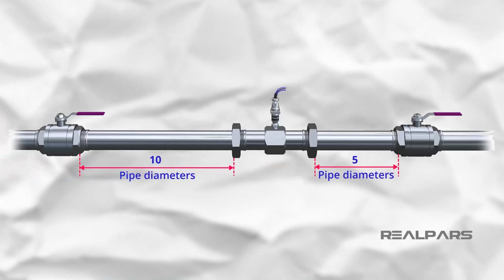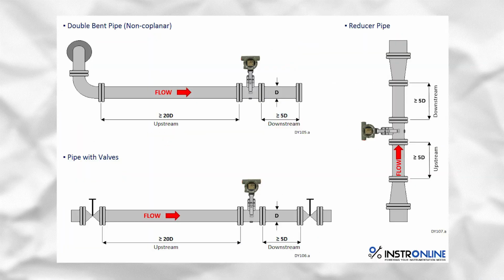To calculate the bore diameter of an orifice, ISO standard 5167 is applied. As an instrument engineer, you should be able to work with related software to do flow element sizing, such as Conval and InstruCalc. The outcome of this software shows the orifice bore diameter and beta ratio, which is the bore diameter divided by the pipe internal diameter. By means of this relation and knowing the fitting installed on the flow element upstream, we are able to estimate the upstream length. You need to bear in mind that in many types of flow elements, fluid turbulence has an intense effect on measuring. Therefore, you need to consider a suitable distance after a fitting like an elbow, T, or reducer to let the fluid profile become laminar.